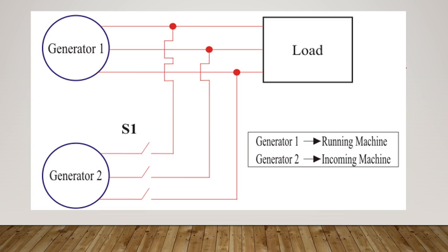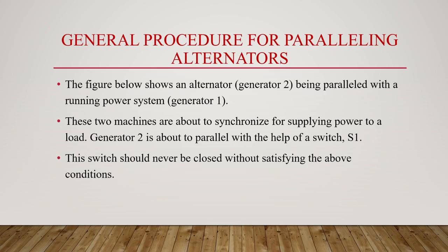Now, this figure shows two generators, generator 1 and 2. Generator 1 is a running machine, 2 is an incoming machine, and they are connected to a load. The figure shows generator 2 in parallel with the running power system generator 1. These two machines are about to synchronize for supplying power to a load. Generator 2 is about to be paralleled with the help of switch S1.